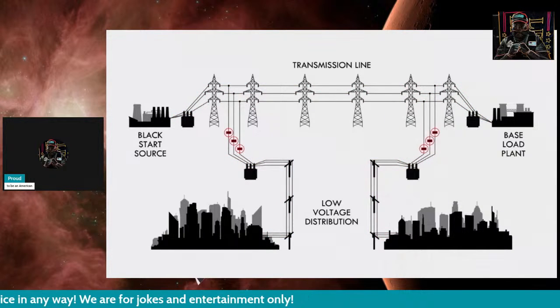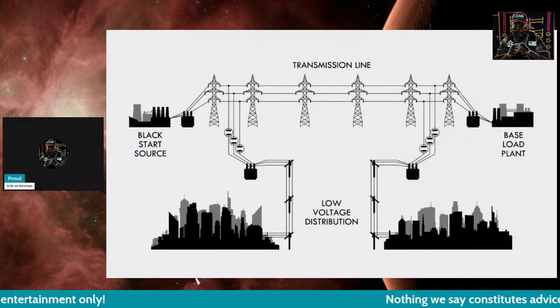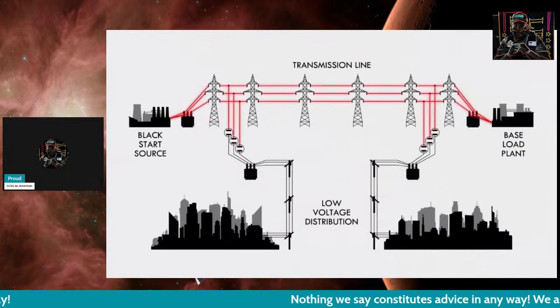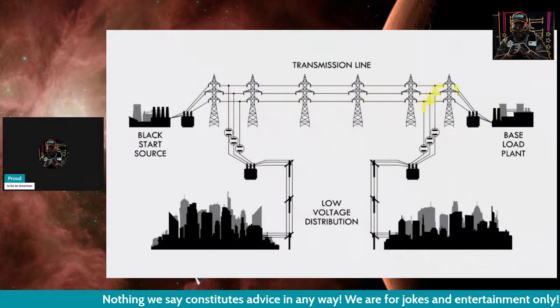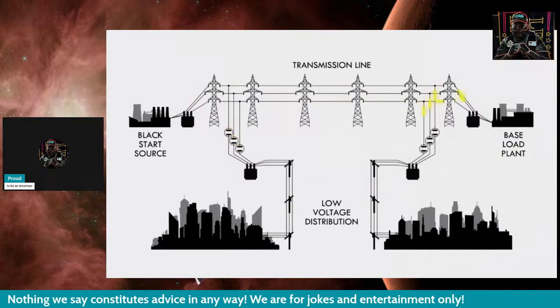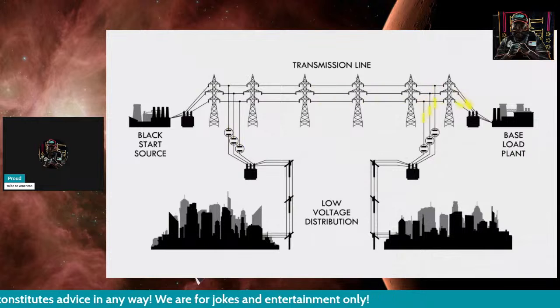All the substations along a predetermined cranking path disconnect their transformers to isolate the transmission lines and create a direct route. Once the black start source starts up and energizes the cranking path, a baseload power plant can draw electricity directly from the line, allowing it to spin up.